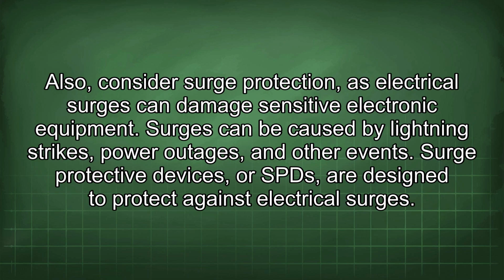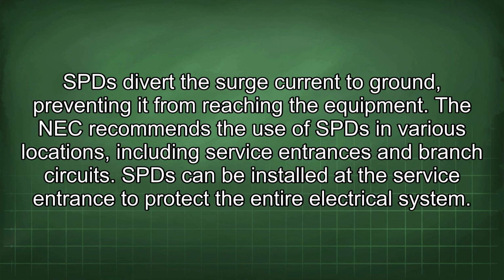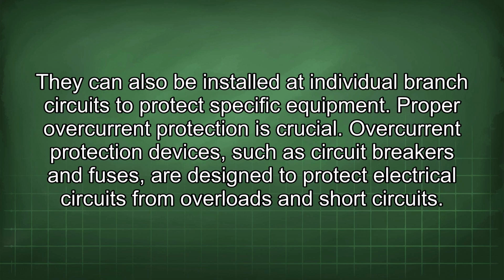Also, consider surge protection, as electrical surges can damage sensitive electronic equipment. Surges can be caused by lightning strikes, power outages, and other events. Surge protective devices, or SPDs, are designed to protect against electrical surges. SPDs divert the surge current to ground, preventing it from reaching the equipment. The NEC recommends the use of SPDs in various locations, including service entrances and branch circuits. SPDs can be installed at the service entrance to protect the entire electrical system. They can also be installed at individual branch circuits to protect specific equipment.